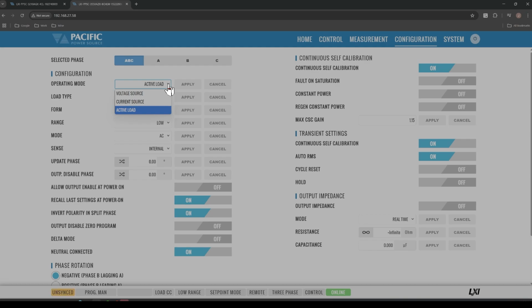We've got choices of voltage source, current source, and active load. We definitely want the active load. We're going to set this one up as a constant current source, or constant current load. It's in 3-phase, voltage range is on low, and we are in AC mode.